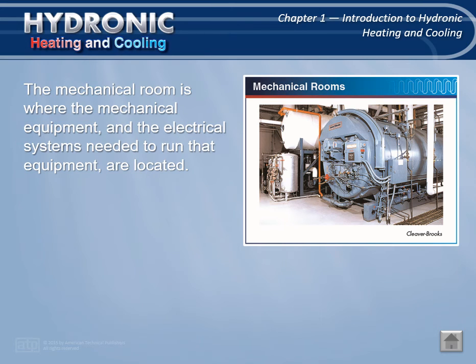When talking about the three main parts of a typical hydronic water heating and cooling system, the typical modern hydronic heating and cooling system is divided into three main parts: the heating and cooling sources, the distribution system, and the terminal units. Each of these is normally installed in different areas of the building: the mechanical room, hallway ceilings and other out-of-sight building areas, and the building spaces or rooms, respectively.